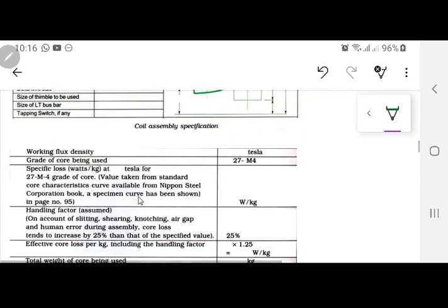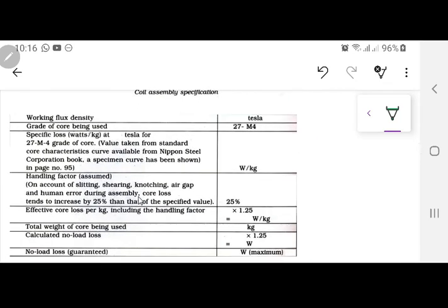Then afterwards, the next calculation comes on for the no load loss. हमने weight निकाला था अभी iron का, which was 200 something or 190. We still don't decide on this one. So over here we have to find out the working no load loss over there. And by no load loss, I am concerned about the hysteresis and eddy current loss. Remember, whenever we are doing an open circuit test, we are measuring the hysteresis and the eddy current loss. We are not measuring the magnetization loss, which is in terms of VA.